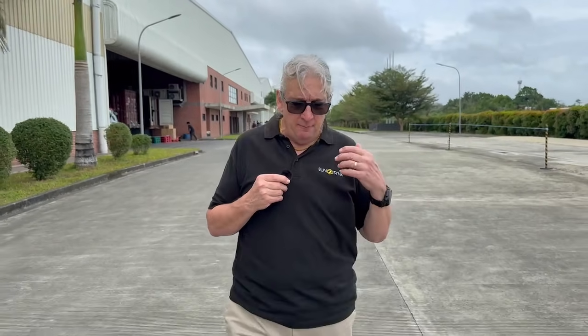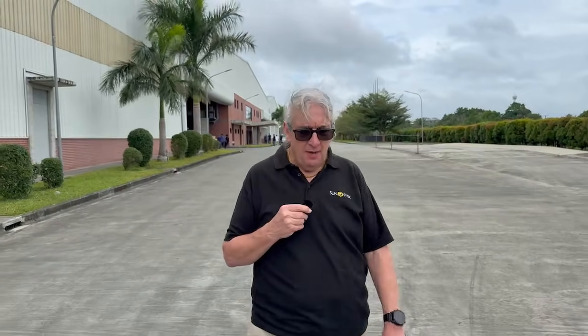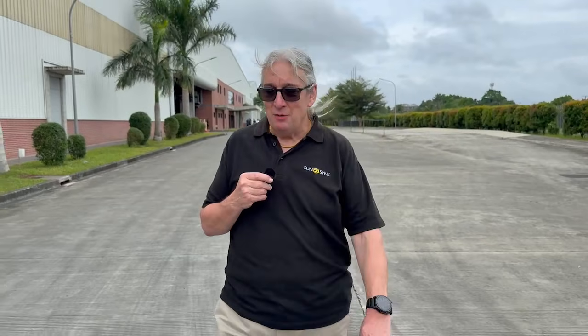Each of the units will have a separate power hub, so we're looking to put a power hub which will just be the MPPTs, and another power hub which will just be the PCSs. They're actually using Delta Grid, so it's 460 volts coming in. We'll use a transformer to couple it, a 460 volt transformer to our PCS, and we'll also output it with a transformer. We're using silicon steel transformers, so super duper efficient.